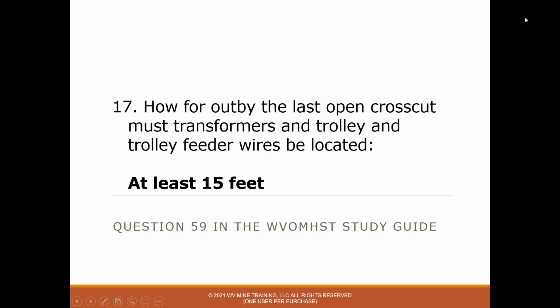17, how far out by the last open crosscut must transformers and trolley feeder wires be located? The trolley feeder wire is just a wire coming off the trolley wire, and these are not permissible. All these items are not permissible, so they have to be at least 15 feet out by the last open crosscut.